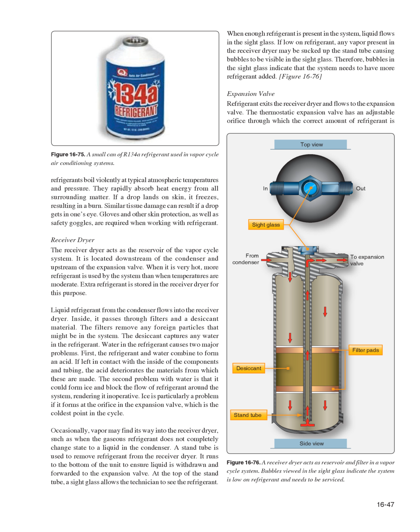Receiver dryer. The receiver dryer acts as the reservoir of the vapor cycle system. It is located downstream of the condenser and upstream of the expansion valve. When it is very hot, more refrigerant is used by the system than when temperatures are moderate. Extra refrigerant is stored in the receiver dryer for this purpose. Liquid refrigerant from the condenser flows into the receiver dryer. Inside, it passes through filters and a desiccant material. The filters remove any foreign particles that might be in the system. The desiccant captures any water in the refrigerant.